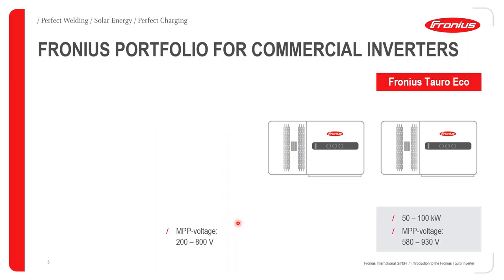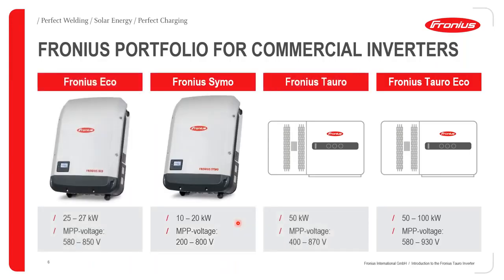Okay, let's meet the inverter. So in terms of our commercial range, we will, in a few weeks' time, have 4 inverters that are tailor-made for the commercial PV sector. Starting off with the Fronius Eco, which will still be on the market for many more years to come. And the reason for this is due to the sheer popularity of this Eco inverter. It comes in power classes of 25 or 27 kilowatts, and your MPPT voltage range is between 580 volts to 850 volts DC. Then having a look at the Fronius Symo, which again will stay on the market for many more years to come. It's in the power variance of 10 to 20 kilowatts, and the MPPT voltage range is from 200 to 800 volts DC.